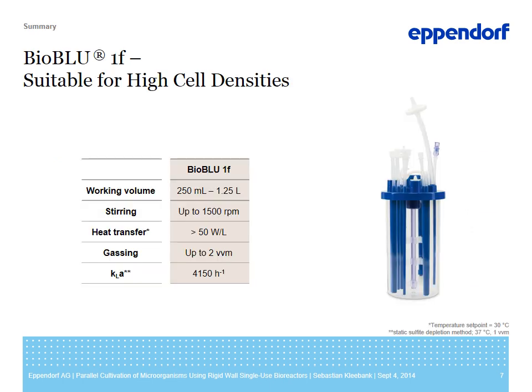Now I would like to give you 2 take-home messages. The first take-home message is that our BioBLU 1F bioreactor is suitable for high cell density cultivations. The stirrer speeds of up to 1500 RPMs combined with the cooling baffles that we have lead to high mass transfer rates. So we could measure KLa values of more than 4000 per hour using the static sulfite depletion method. Also, due to the cooling baffles, we reach heat transfer rates of more than 50 watts per liter. This means we can effectively get rid of the biological heat that is formed especially during high cell density cultivations.